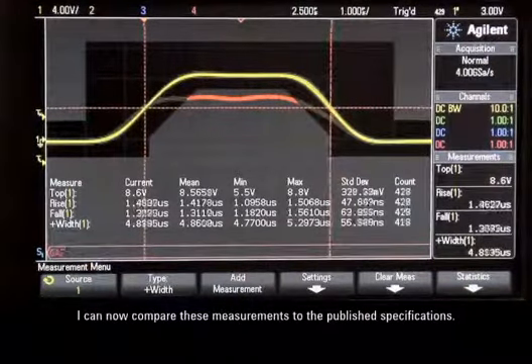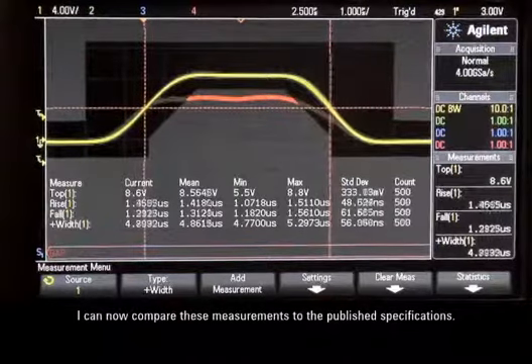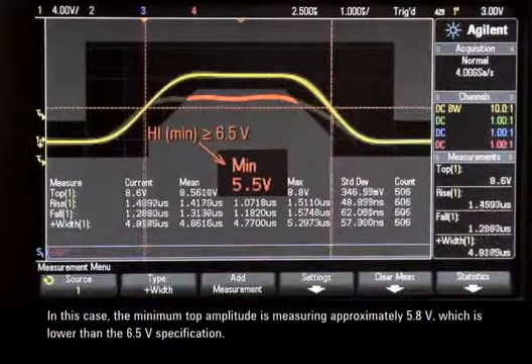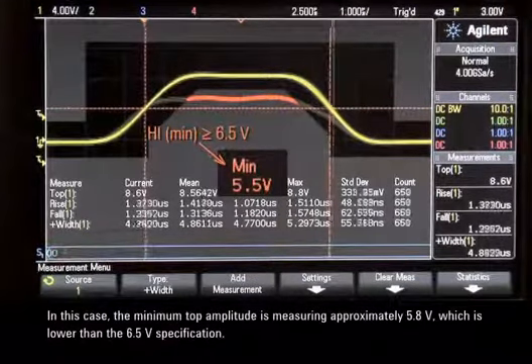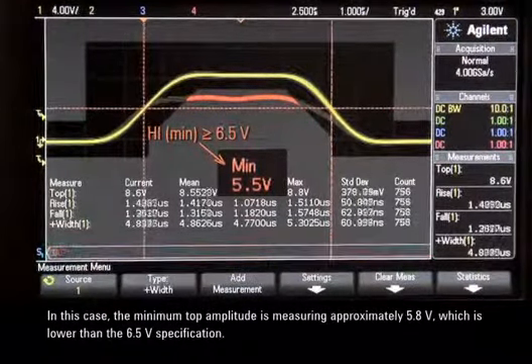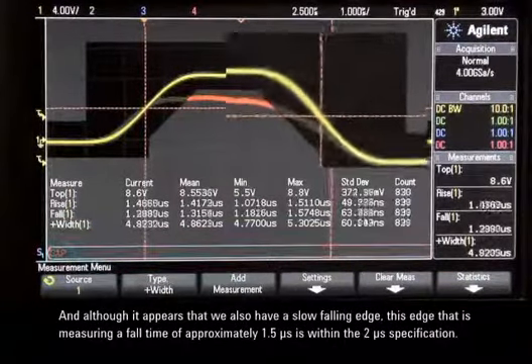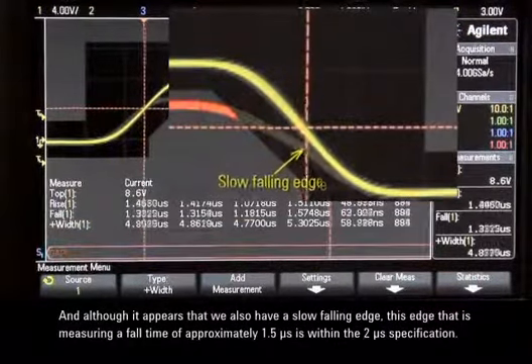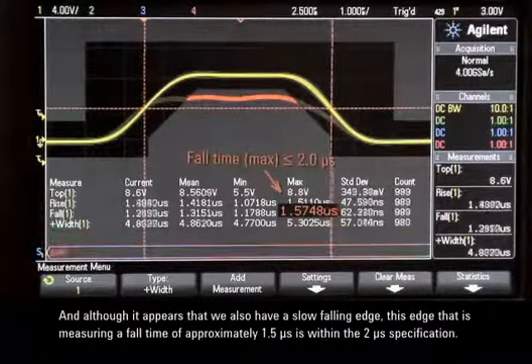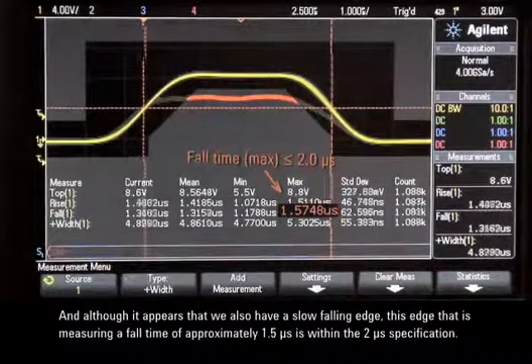I can now compare these measurements to the published specifications. In this case, the minimum top amplitude is measuring approximately 5.5 volts, which is lower than the 6.5 volt specification. And although it appears that we also have a slow falling edge, this edge is measuring a fall time of approximately 1.5 microseconds, which is within the 2 microsecond specification.